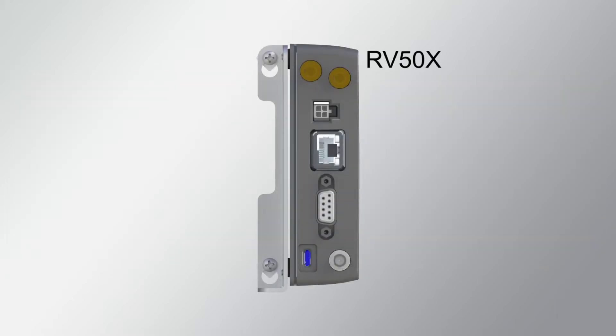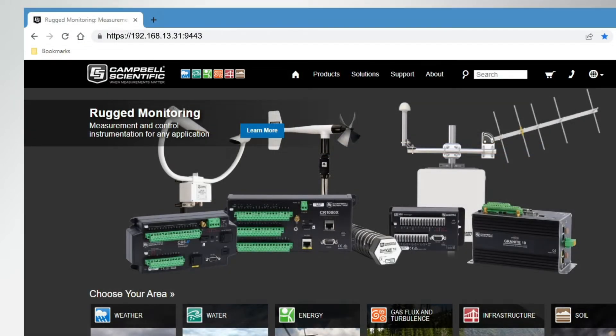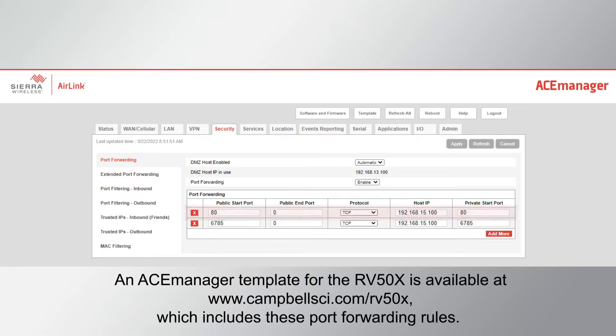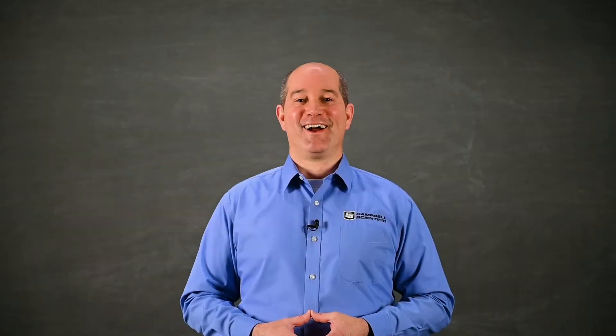Ace Manager is a built-in web page in the RV50X used to configure the modem. It is accessible by connecting the RV50X to a computer with an Ethernet cable, then entering HTTPS://192.168.13.31:9443 into a web browser. We need to set up a rule that will forward incoming requests from outside the local network to specific hosts in the local network when the request comes in through a specific port. The first rule will forward any requests coming in on port 80 to the internal address 192.168.15.100 port 80, which is port 80 on the CR1000X datalogger.